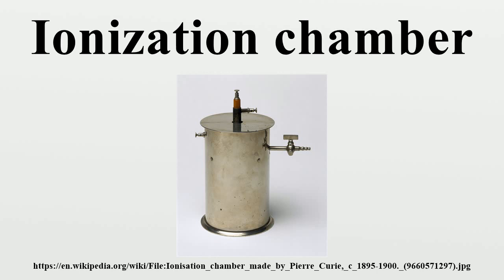Vented chamber: These chambers are normally cylindrical and operate at atmospheric pressure, but to prevent ingress of moisture a filter containing a desiccant is installed in the vent line. This is to stop moisture building up in the interior of the chamber, which would otherwise be introduced by the pump effect of changing atmospheric air pressure. These chambers have a cylindrical body made of aluminium or plastic a few millimetres thick. The material is selected to have an atomic number similar to that of air, so that the wall is said to be air equivalent over a range of radiation beam energies.